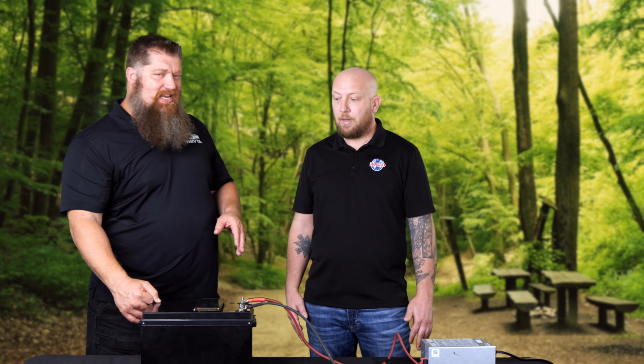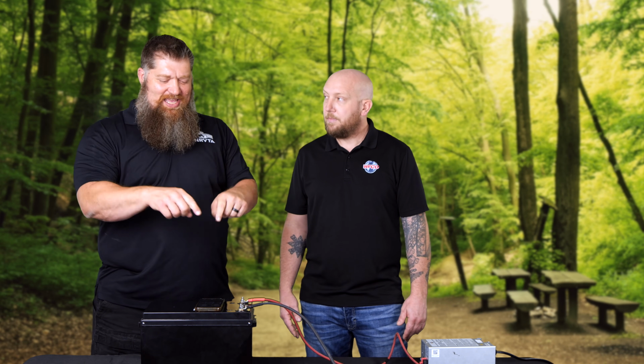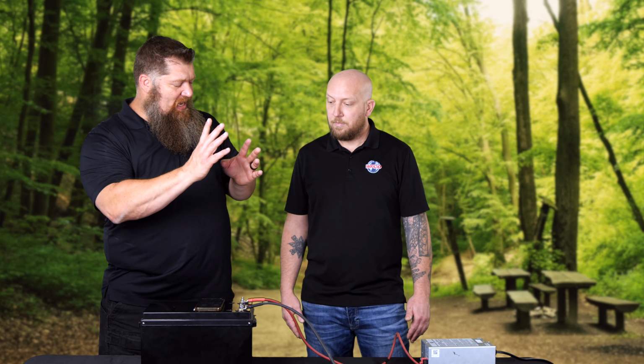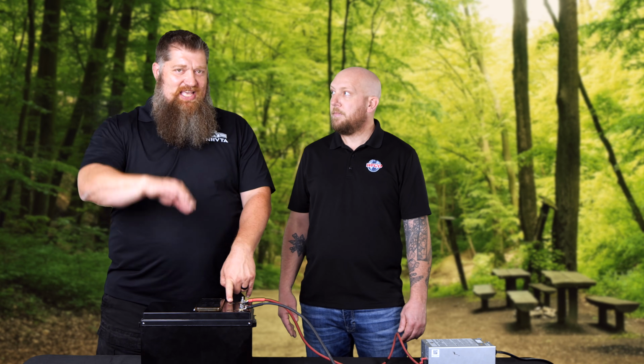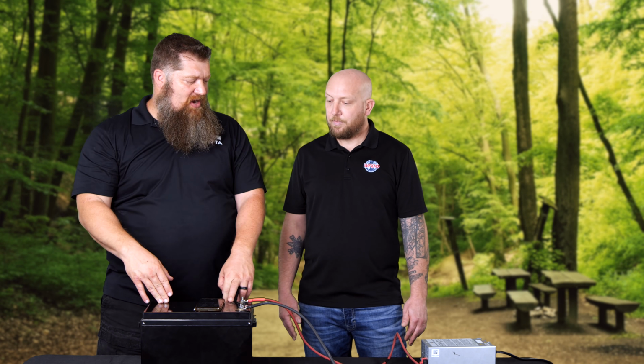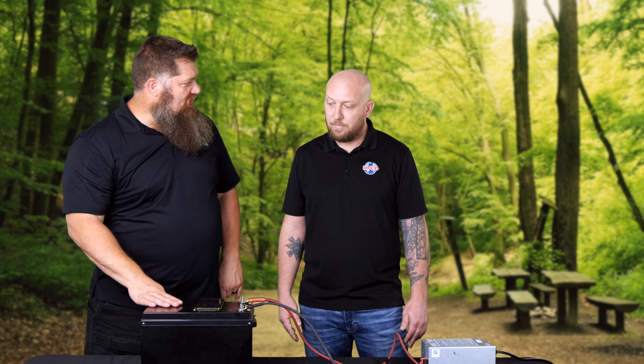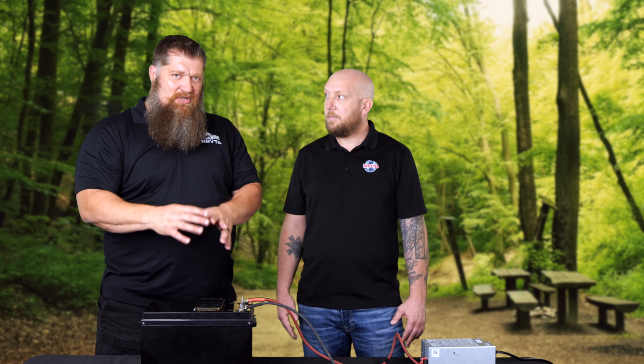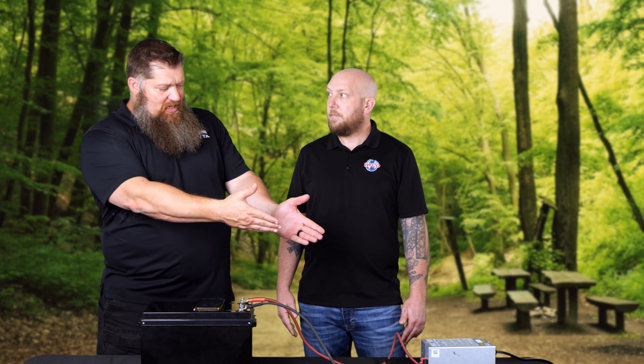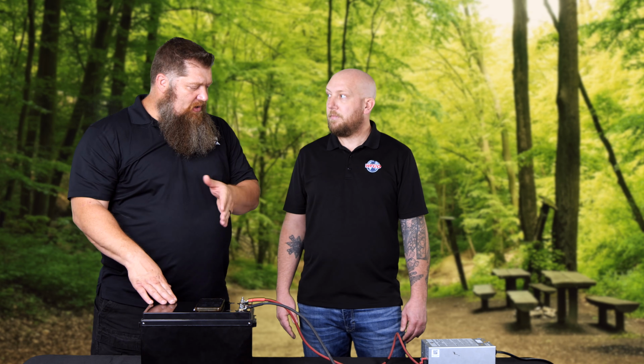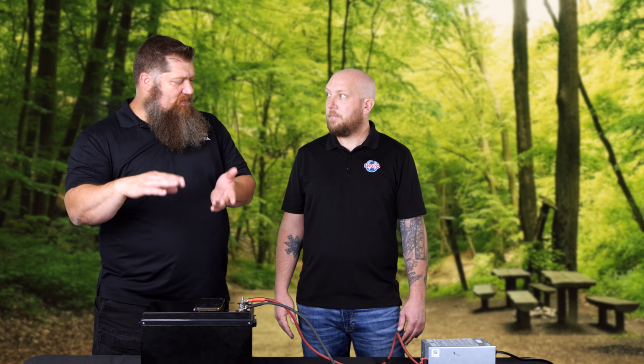He forced it into lithium by disconnecting it and plugging it back in. We told the system we're charging, then cut power - it identifies that drop-off as a lithium battery. So we plugged it back in, went straight to blue, and still got the same 50 amps. So even if it's green, it doesn't lower the amperage or take longer to charge - it's still going to go at whatever maximum capacity that converter can do. You just get a green or blue light, or as you're saying, 14.6 or 14.4.